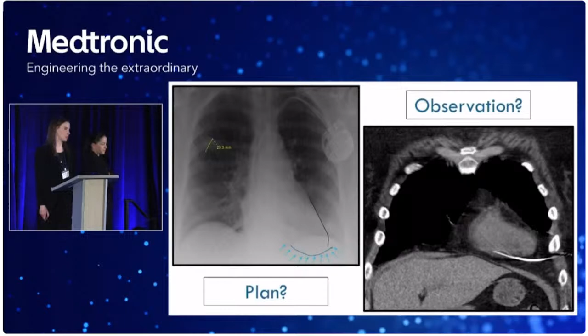So failure to capture can happen for a lot of different reasons. Sometimes it's our fault, sometimes it's not. So there can be generator failure. Maybe you've put the lead in the header poorly. Maybe you've just programmed it wrong. If you program it subthreshold, it's not going to capture either, or you don't give a safety margin with your programmed output. Lead dislodgement can certainly lead to failure to capture, as could lead fracture.